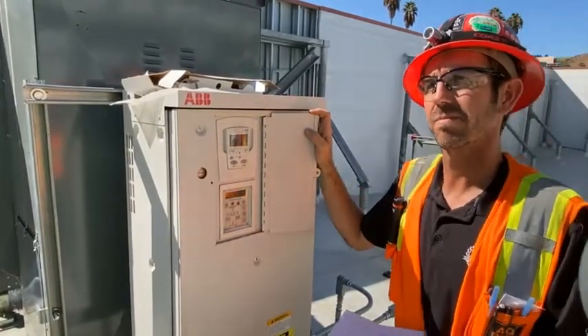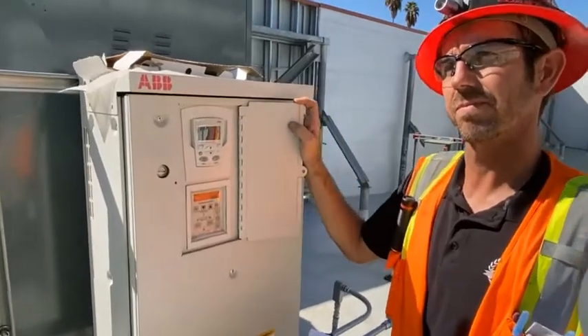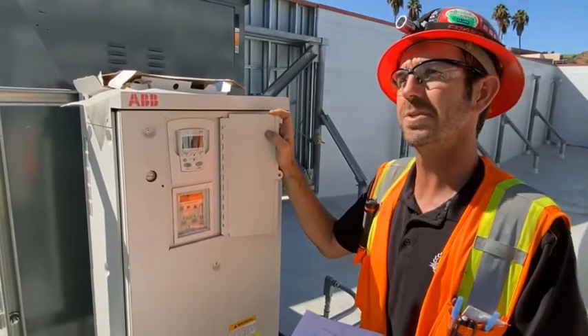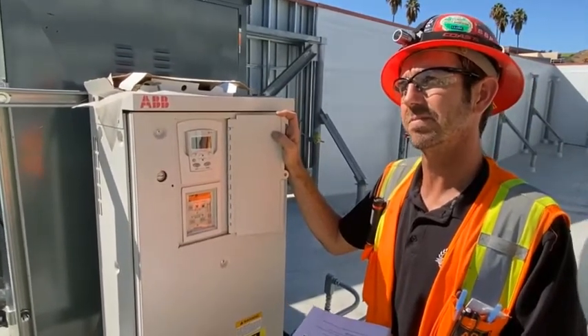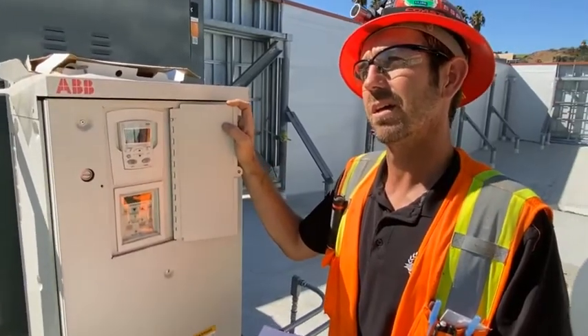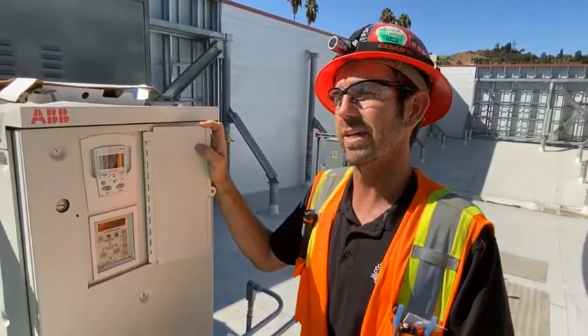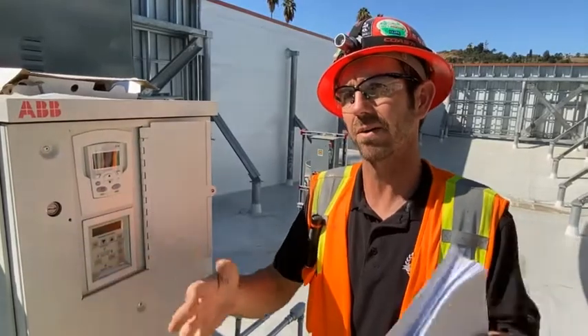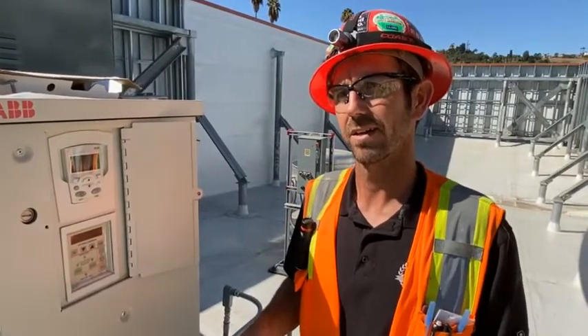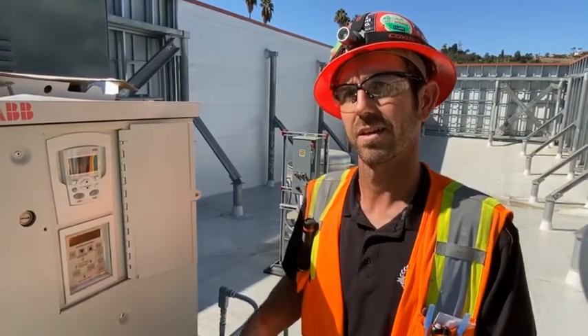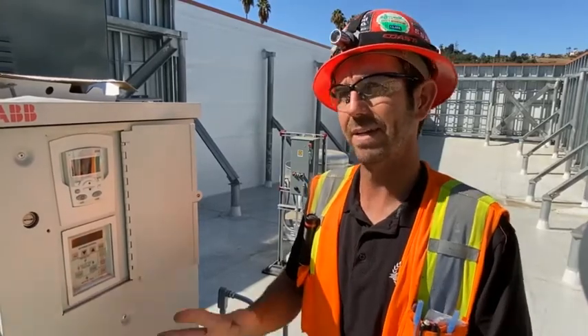Yeah, I understand. It's just that the reason for the frequency drive is to vary your speed, so it's an option. If you've got more airflow down here than you need, you spin it down; if not, it slows it down. So it's a constant volume system though. Right, but no instruments are reading it. It's not checking, we're not maintaining any static pressures.